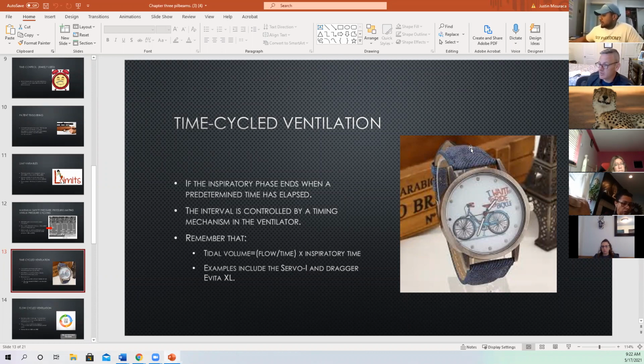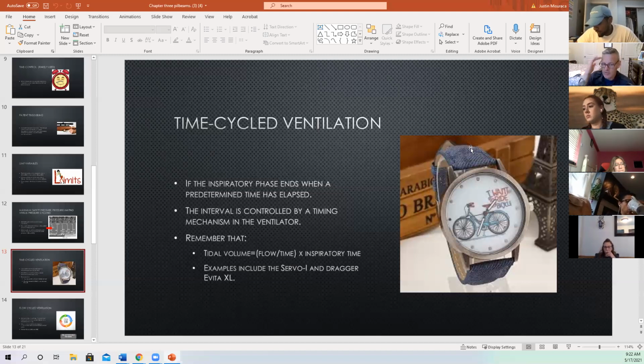Time cycle ventilation. Inspiratory phase when it ends. So if I set an I time and it's at 1 second, that breath goes in for 1 second. Once I hit that 1 second, the ventilator stops delivering flow. It rotates into exhalation. The patient begins to exhale. What's cool about these things, it's not tricky, right? They'll say, like, pressure limited, time cycled.